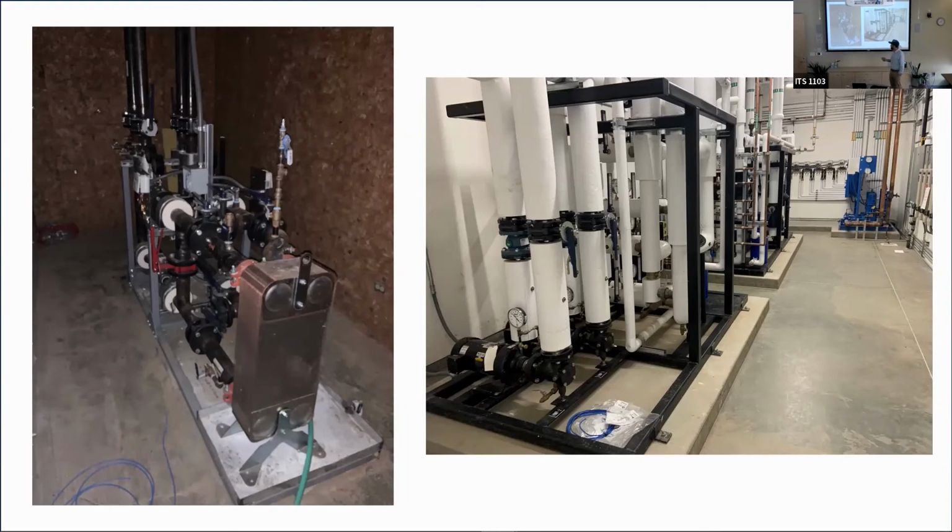In new buildings, we actually can run that hot water from the loop directly into the building. But in the older ones, we put a plate frame or a brazed plate heat exchanger there because of concerns about building water chemistry and problems in the building if we run new water into the building. So most or about half the buildings have a heat exchanger, and this shows a new building, our teaching and learning complex, with some new connections to the district heating and cooling. That was our first building to be directly connected to the hot water system without ever being connected to steam.